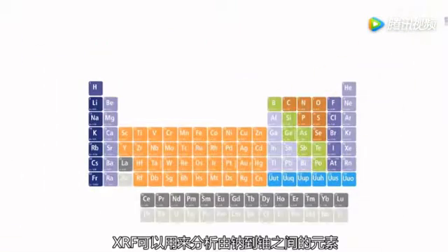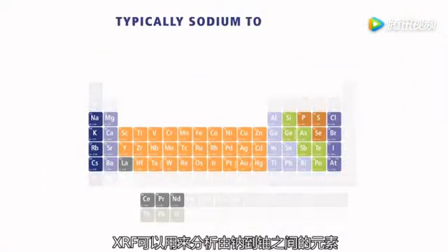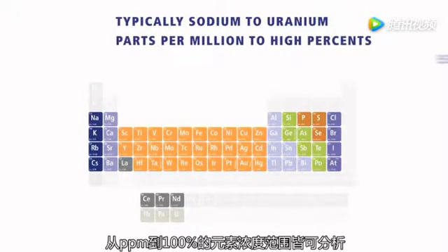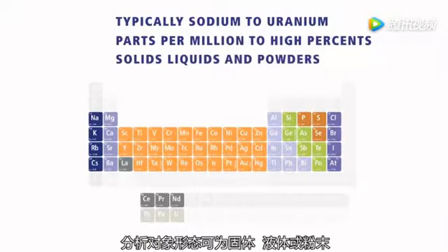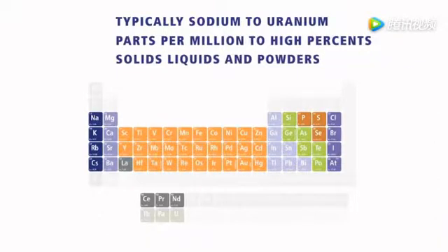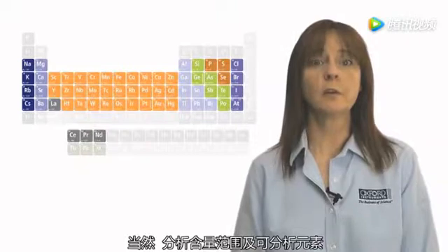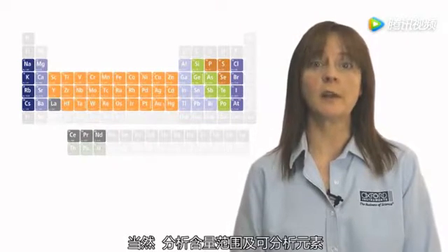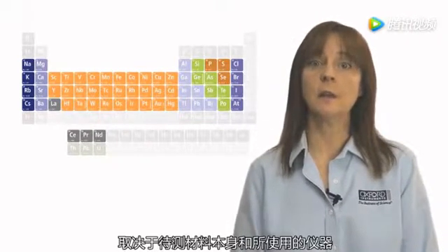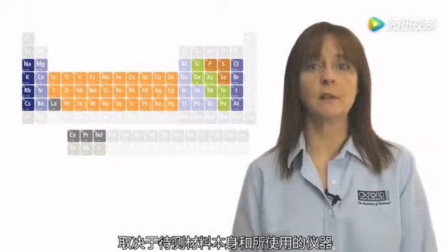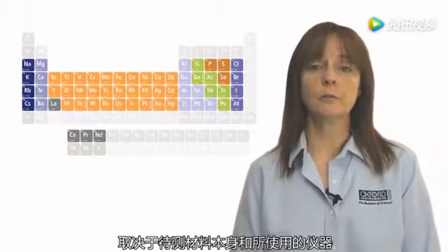XRF can typically analyze elements from sodium to uranium in concentrations ranging from parts per million to high percents in solids, liquids, and powders. The elements and concentrations that XRF analyzers can determine depend on the material being tested and the instrument used.